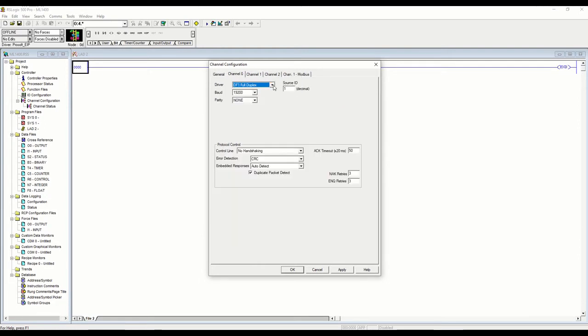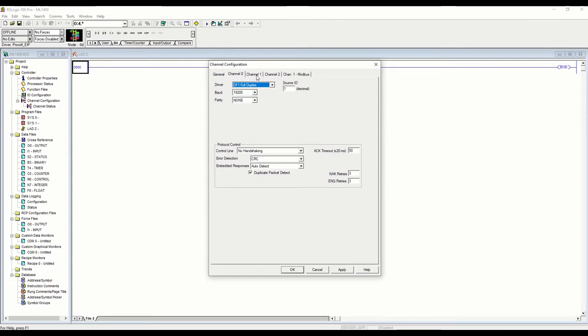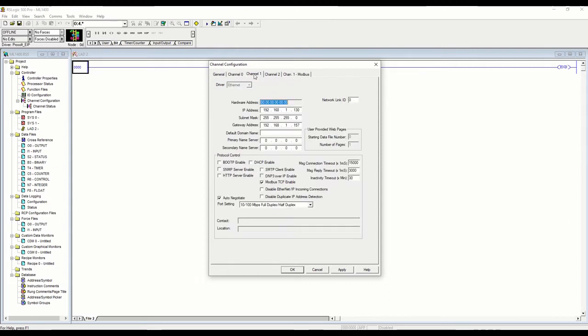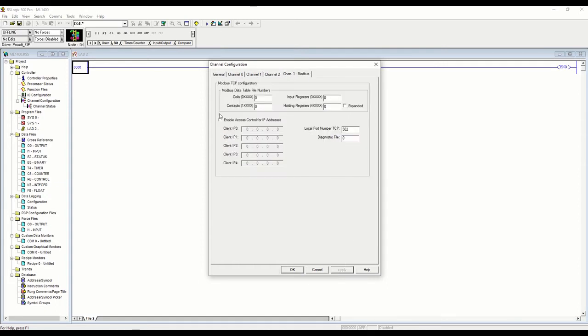If we did want to do this over Modbus serial, we could do that over the serial port as well — you just tell it if it's the master or slave. In this example we're going to use TCP, so we enabled that and we'll hit apply. Then over here you'll see this extra tab appears. This is for the case where this device acts as a Modbus slave — we would map data files to the holding registers or coils.